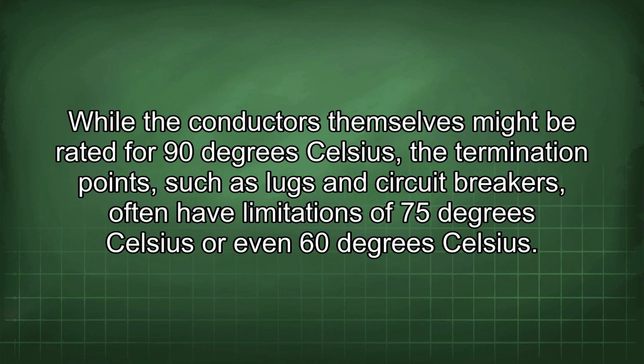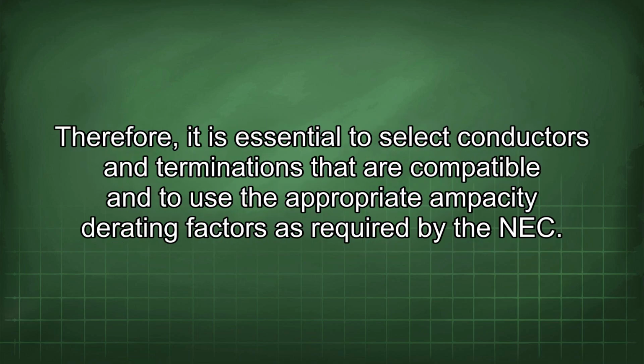While the conductors themselves might be rated for 90 degrees Celsius, the termination points, such as lugs and circuit breakers, often have limitations of 75 degrees Celsius or even 60 degrees Celsius. Therefore, it is essential to select conductors and terminations that are compatible and to use the appropriate ampacity derating factors as required by the NEC.